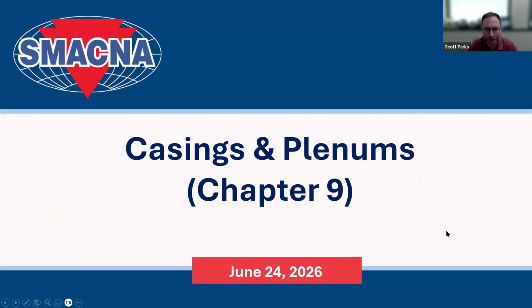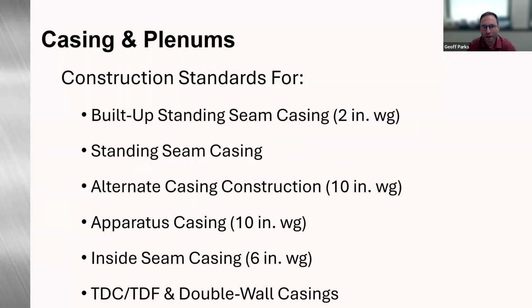Okay, moving on. Casings and plenums. This is covered in Chapter 9 of the standard. So what we have in here, we have construction standards for built-up standing seam casings up to 2-inch water gauge, standing seam casings, alternate casing construction up to 10-inch water gauge, apparatus casing to 10-inch water gauge, inside seam casing, and then TDC, TDF, and double wall.